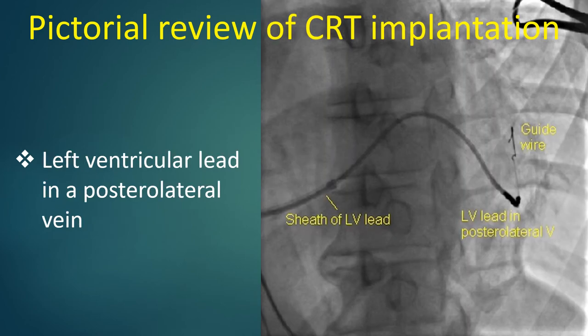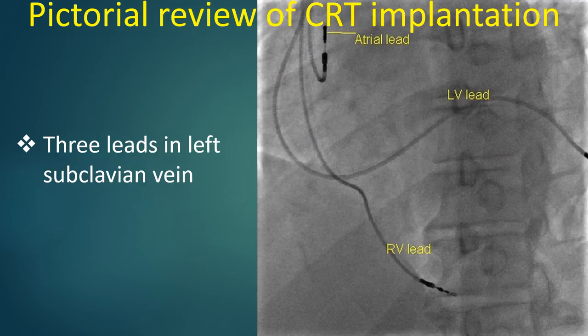The left ventricular lead of the CRT device can be threaded over the guide wire into the posterolateral vein. The peel-away sheath can be split using the device provided in the kit once a stable lead position has been obtained and tested. The atrial lead can then be introduced and positioned in the right atrial appendage.